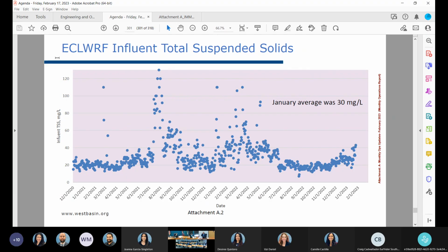What this water quality and turbidity and suspended solids does to the membrane is bring a lot of fouling, which ends up requiring a lot of pinning activities. That takes a unit down, meaning reduced production. At the satellite facility, the CEMS is being constructed. Hopefully by August we won't be impacted as much, because the satellite facility MF still uses polypropylene membranes, which are not as easily cleaned and take a lot more effort to clean and pin.